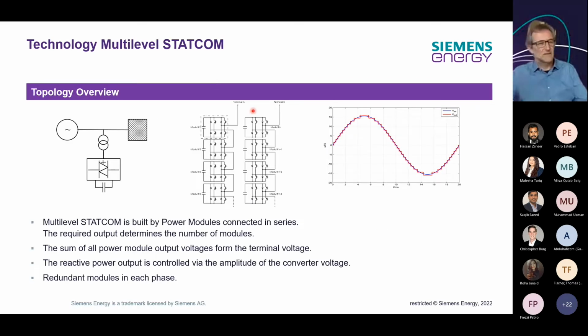How does it work? The converter itself, we are using IGBTs. We use a number of IGBTs, which are controlled individually. And each of these submodules will have a DC capacitor with a certain voltage. And by switching those IGBTs, we can sum up the DC voltage and we can generate this nice little sinusoidal wave. And we can see the steps are quite small. This is to make sure you will not apply more harmonics into the system, or at least keep it to a minimum.